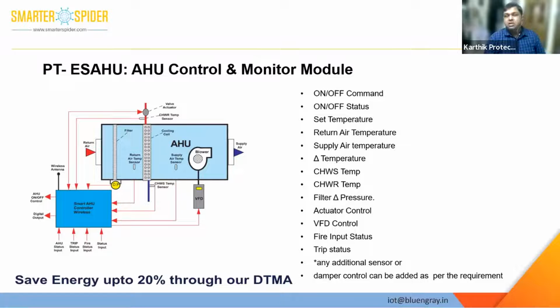If it's a ductable type AHU, then we have an on-off command, the on-off status, set the temperature, measure the return air, measure the supply delta T of it, then unit on-off control as well as compressor on-off control along with the filter pressure. Now, there are some hospitals where you may say, okay, we already have an existing BMS system, but that is restricted to only on-off, and you don't have the capacity to control the chill water.